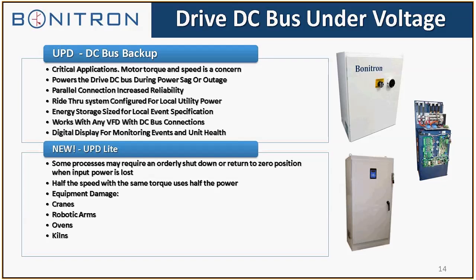A good example is robotic arms, things like that. If you lose a reference or lose a drive completely, the robotic arm can damage equipment or cause personnel injury. So that's why sometimes the customer doesn't want full power ride-through. They don't care if the system shuts down. They just want to be able to shut it down in an orderly manner. So it's usually sized for half the speed with the same torque. It's a calculation involved. If we're going to do UPD Lite, it's always an engineered solution, but it's a possibility if the customer is asking for it.